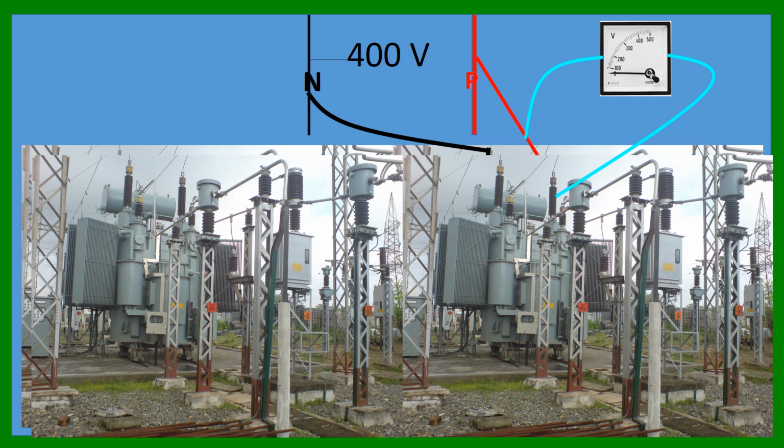This is the system. Now if the voltage is showing 324.24 volt, that means subtractive, 400 minus 75.76, then it is the same phase. That means both the HV side and LV side across the voltmeter are phase. But if it is not subtractive, it is additive, then the voltmeter HV side is phase and the voltmeter LV side is neutral. This is the system. Take care and check it. Okay, thanks today.